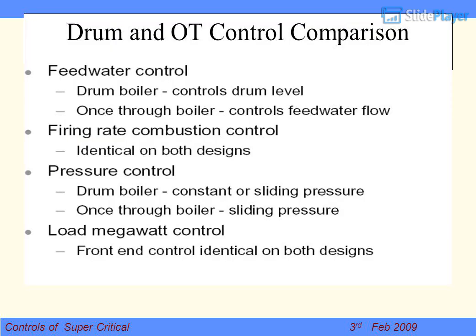Drum and Once-Through Unit (OTU) control comparison. Feed water control in drum type boilers should be known to you. The drum acts as a buffer and it can work as a three-element or one-element controller. It is one of the most important loops in C&I. Operations always demand this loop to be on AUTO. So the feed water loop controls drum level in drum type boilers; in OTU, feed water controls the feed water flow directly.